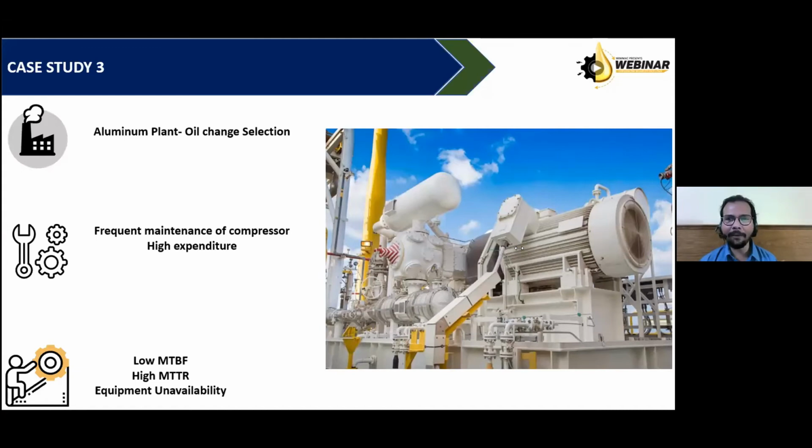After analysis, we found that 80% of the failures were due to oil contamination. Then after analyzing again, we found that the oil selection was not proper for that particular application. Yes, the same compressor would have worked fantastically in a different industry.